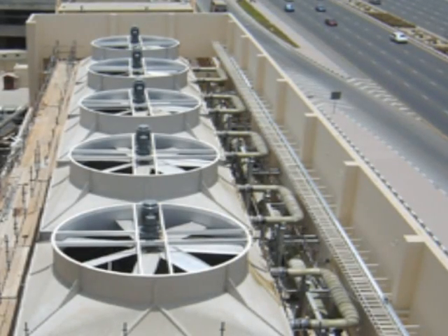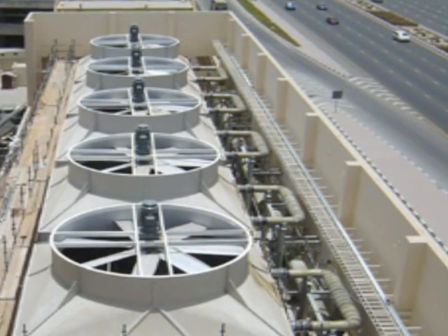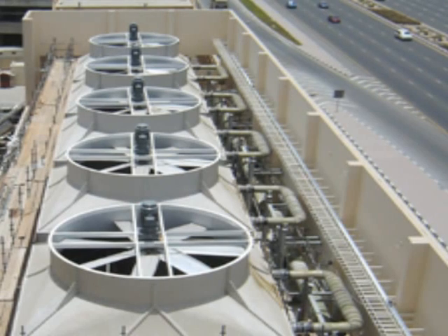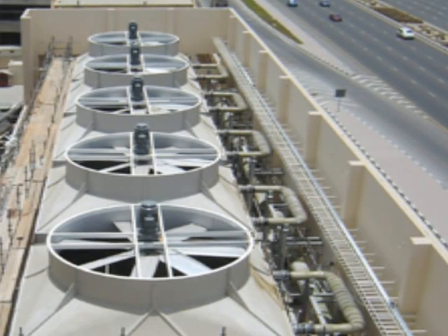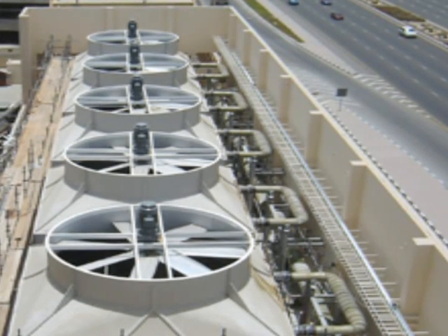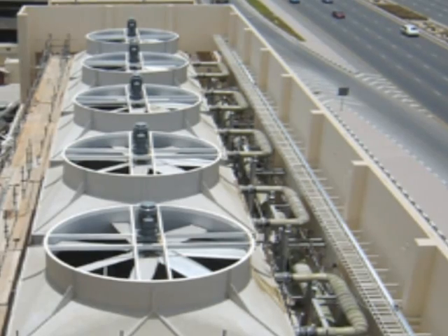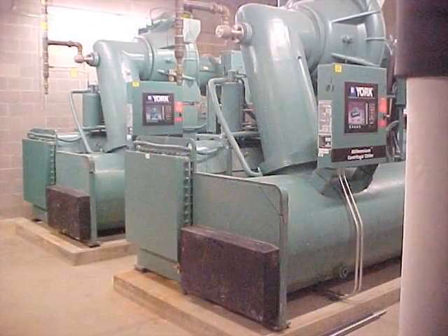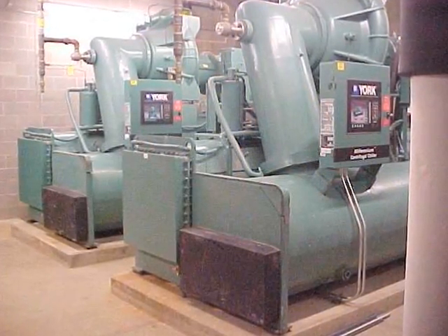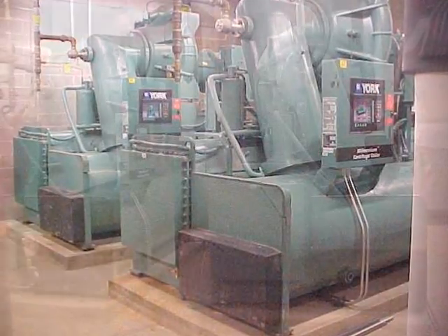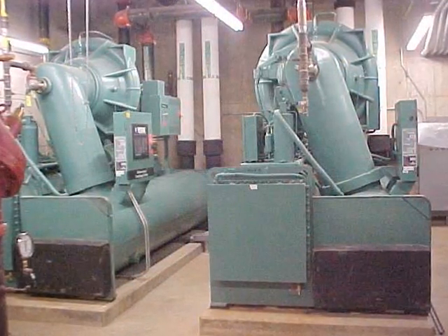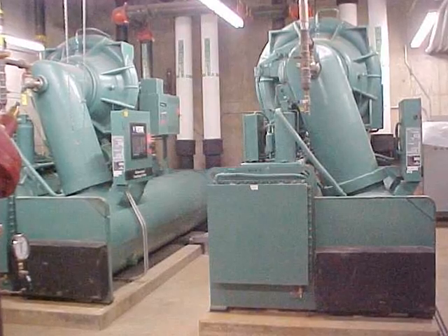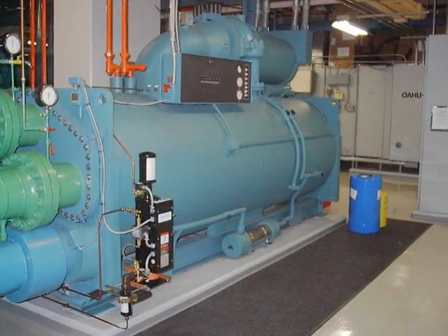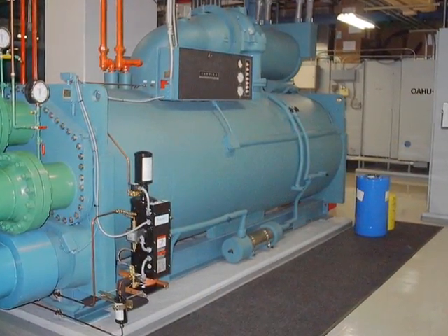Operating scenario type 2. This is the most common category and is typical of chillers where they are subject to frequent loading and unloading conditions. For these chillers, oil migration to the refrigerant charge can be significant. During periods of low load operation, the pressure differential between the low and high side decreases, lowering the effectiveness of the oil return system, or eductor pump, allowing excess oil to accumulate in the refrigerant charge.